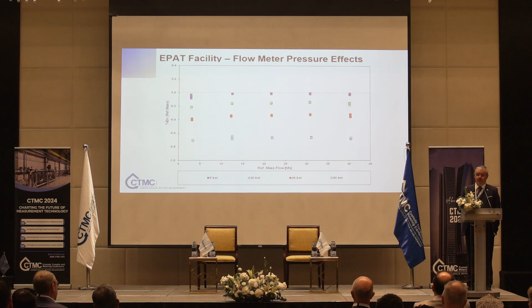Now, I know that nowadays Coriolis meter manufacturers have pressure corrections, but if you're using this for something like custody transfer or allocation, it has to be traceable. So the key advantage of a facility like this is that the details matter. It's not enough to just stick it in a water line calibrated at 5 bar. Details matter. If you want that low uncertainty and you want traceability, you have to be very thoughtful about how you're going to calibrate your meter.